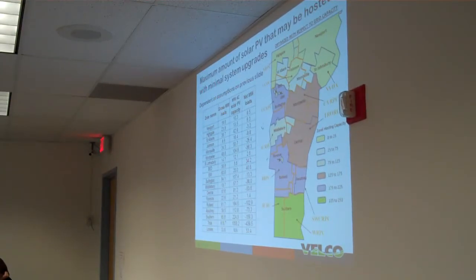Yes. You're losing that right now, just because load is not next to the source. Correct. And so it's the difference between 33.6 and 53.4 that you would lose if you use this scenario for the optimization based on transmission capability. Correct, exactly. And that 53 is lower than we've seen in the past. So this was, say, a 20 megawatt delta in losses. So it's 20 megawatts in incremental losses because of 1,000 megawatts of solar PV, compared to what was, I think, 86 megawatts in the prior distribution. So by distributing solar PV in this way, you have lower losses than if you use the current distribution of solar PV. It's a better, more spread out way of doing it.